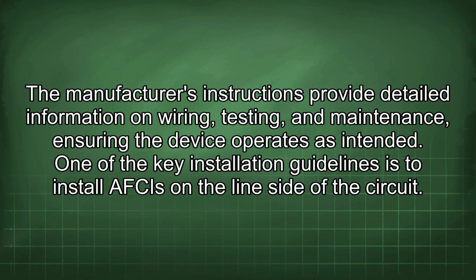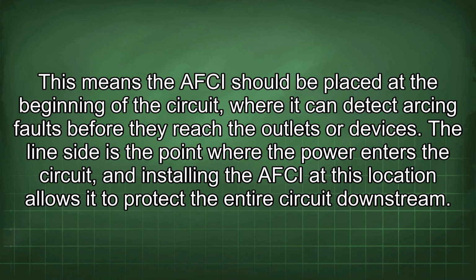One of the key installation guidelines is to install AFCIs on the line side of the circuit. This means the AFCI should be placed at the beginning of the circuit, where it can detect arcing faults before they reach the outlets or devices. The line side is the point where the power enters the circuit, and installing the AFCI at this location allows it to protect the entire circuit downstream.